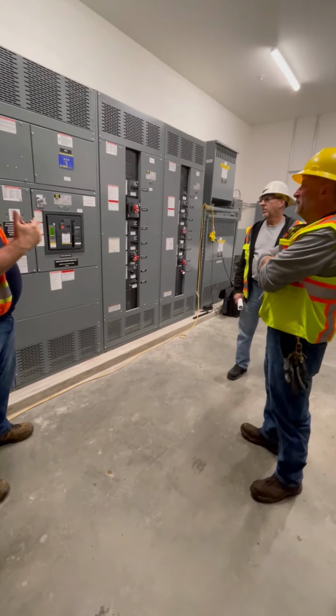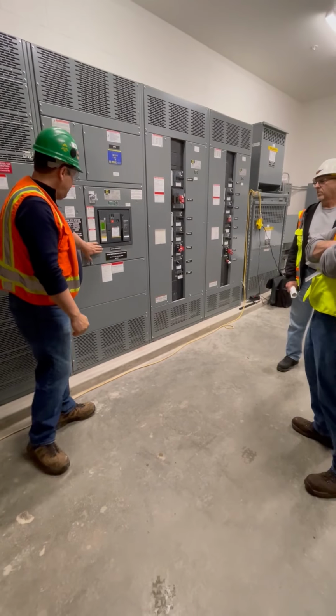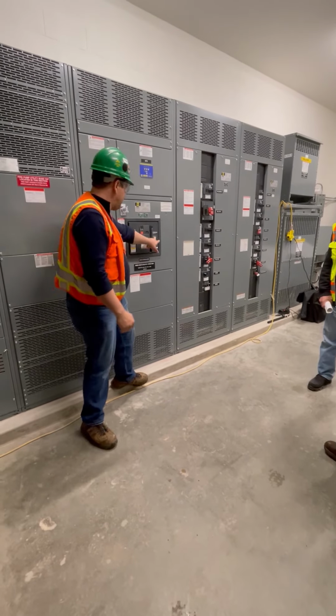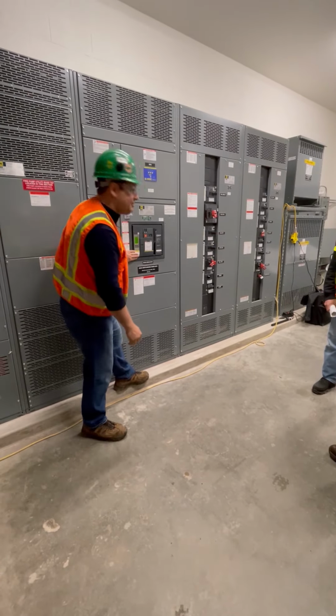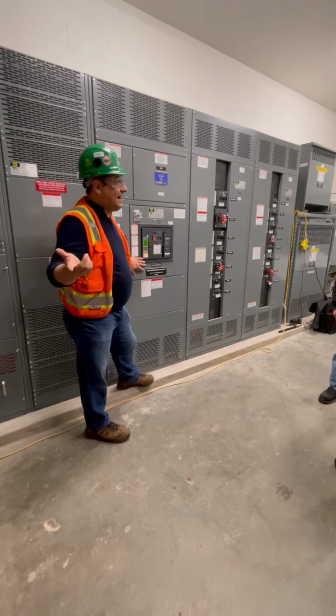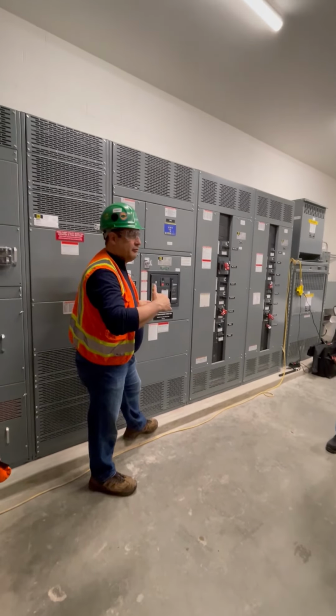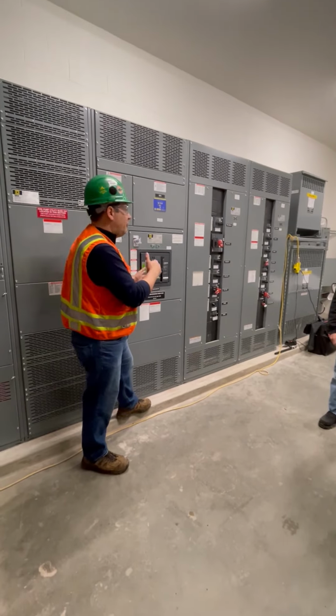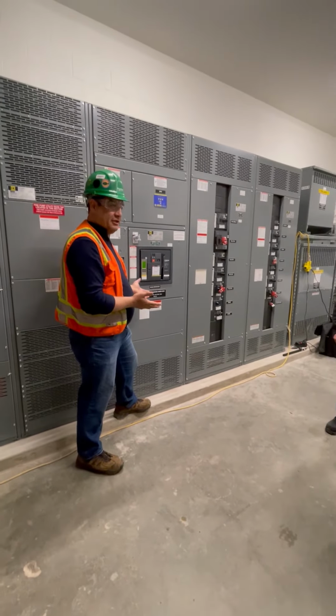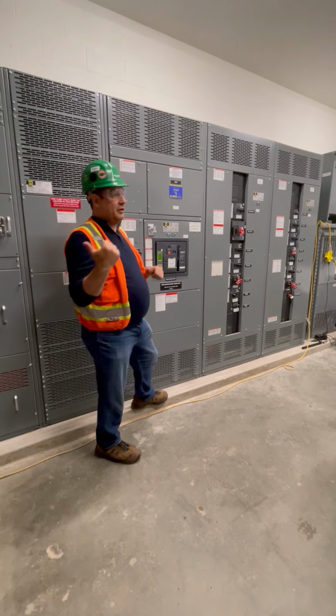Well, what I suggest, so here's the thing. These are set, being at 3,000 amp, is probably set somewhere, depends on what the setting is. 1,200 is the highest, but you can go down to like 300, 400 on the ground fault. So it depends on where it's set. 400 amps, 500 amps, that's when it trips it off, right? It could go up to 1,200, like you said.